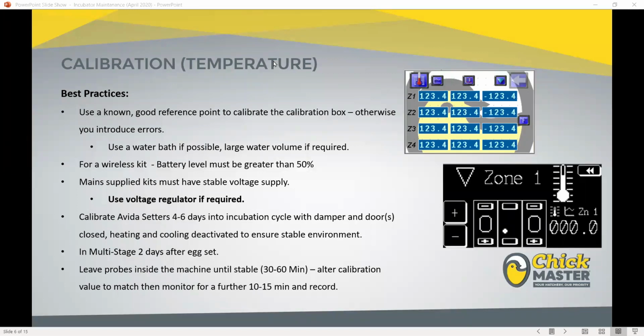If you're fortunate enough to have calibration ports on the roof of your machine, you can drop them straight down to a known length into where the probe location is. Whereas on the older incubators, you may need to go through the doors. If that's the case, calibration is going to take a little bit longer, because once you've opened the doors, you need to let the environment within that cabinet stabilize.